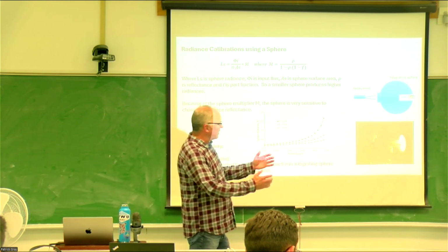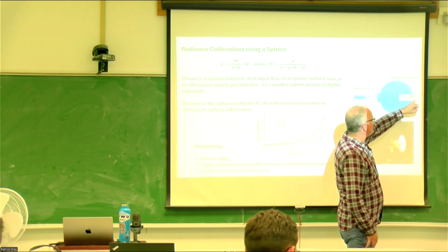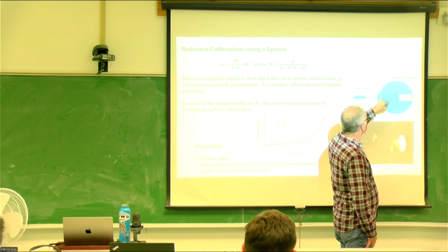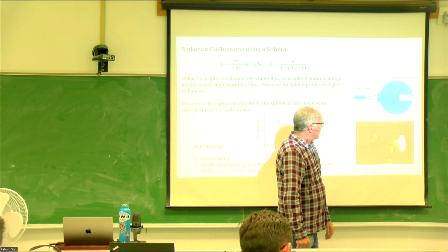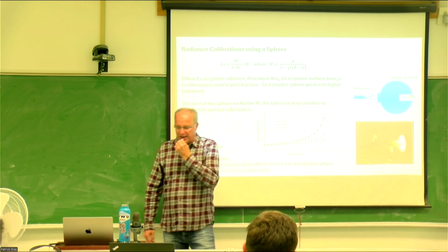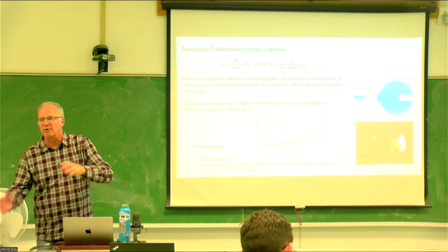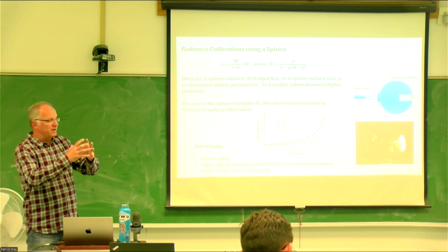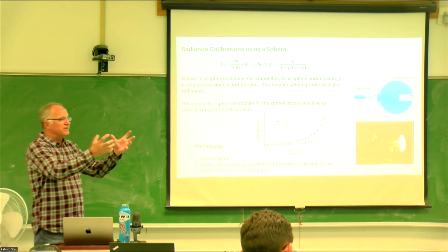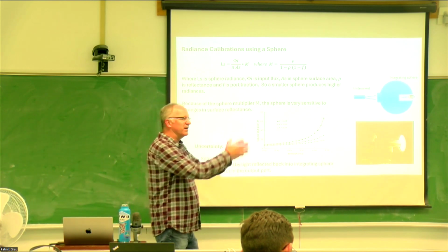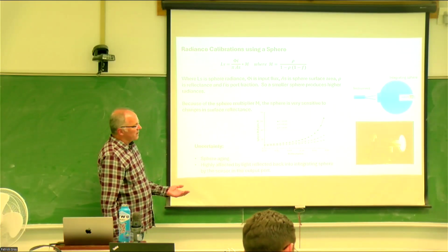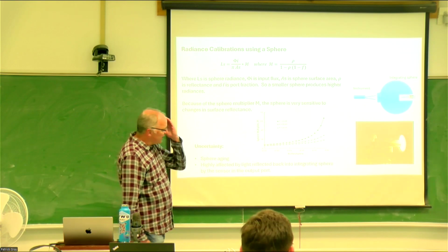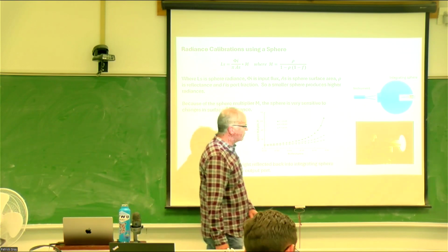So as I put one of these FEL lamps on one side of it into a port, here's the output port from this, an integrating sphere illuminated by an FEL, the light coming out is pretty much now Lambertian style light. It's going equally in every direction. So these are really great to use. They have some other different constraints and cons to them.